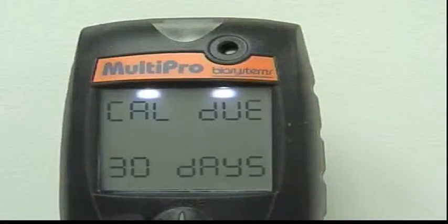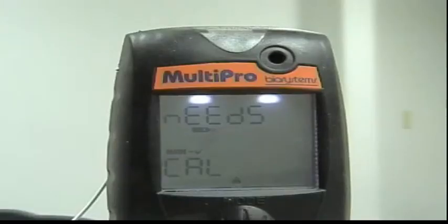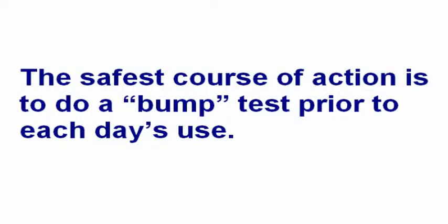All MultiPro gas detectors feature a calibration reminder that is shown when the instrument is turned on and can be set to specific intervals between 0 and 180 days. Biosystems recommends that sensor accuracy be verified frequently. The safest course of action is to verify sensor performance daily. See Appendix B of the MultiPro Reference Manual for official calibration recommendations.